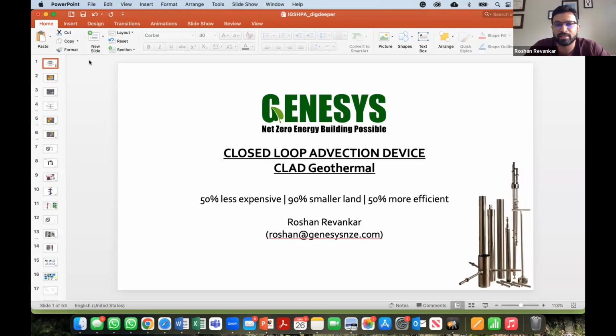On the open loop side, yes, you would need to know the discharge and the drawdowns of the well, which most drillers know. For example, in the project that I showed, the wells were spaced, and maybe this answers one of the questions: what's the spacing between the wells? We've spaced the production wells about 30 feet from each other. And there were tests done to check the water level on the second and the third well. If you were drawing a lot of water, does the first well drop its level? So those kinds of drawdown tests would be needed on large projects, but that can be done on site while the drillers are on site. So that's what happened in our case.